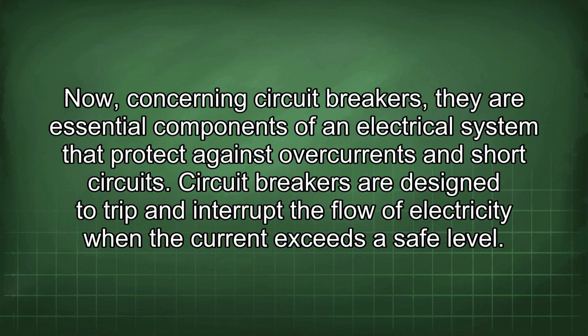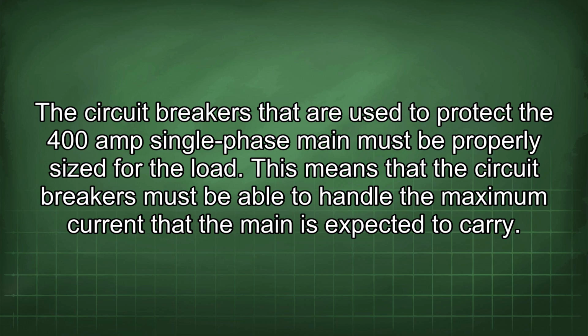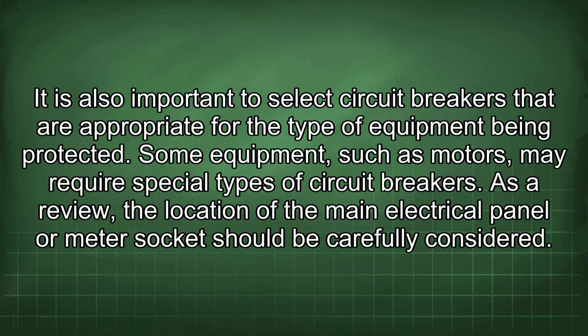Now, concerning circuit breakers, they are essential components of an electrical system that protect against overcurrents and short circuits. Circuit breakers are designed to trip and interrupt the flow of electricity when the current exceeds a safe level. The circuit breakers that are used to protect the 400 amp single-phase main must be properly sized for the load. This means that the circuit breakers must be able to handle the maximum current that the main is expected to carry. It is also important to select circuit breakers that are appropriate for the type of equipment being protected.